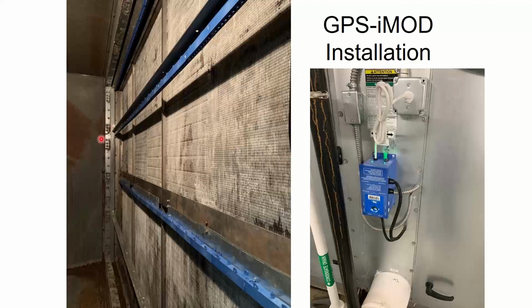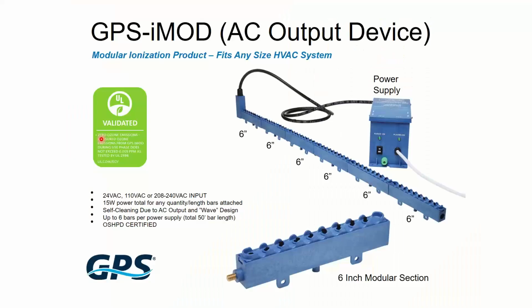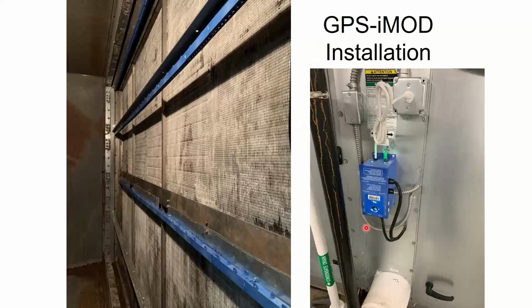When you're changing the filters, at that same point in time, wipe all the needles off. These aren't metal needles like they used to use in the old days to create these charges. They're like a carbon brush, if you will. But they do need to be wiped off because of the electrical charge on them. They attract some dust to cling onto them, and the more stuff that clings on them, the less they can produce and put into the plasma field. So they have to be wiped down every once in a while. That's literally the only maintenance on them.